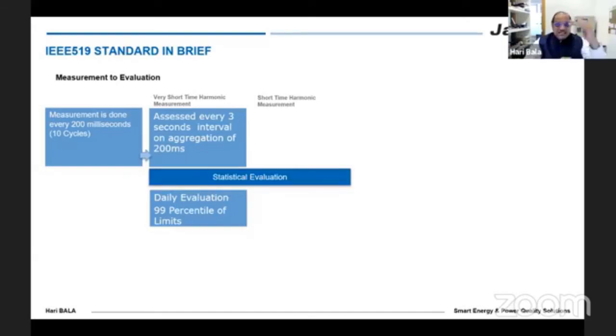So these 28,800 data points collected, for example for TDD, are sorted in a certain order, and then the 99th percentile is found, and then that limit is cross-verified with a table which is given in the standard.